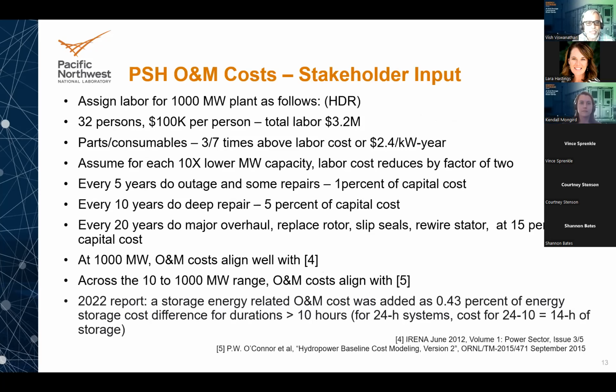For operation and maintenance cost, this is a detailed slide that we also used as a template for compressed air, so I'll go through it quickly. We assign labor for 1,000 megawatts as 32 persons at 100K per person per year, giving total labor cost. Parts and consumables are about 40% of labor cost. We assume that for each 10 times lower megawatt capacity, labor cost reduces by a factor of 2, not 10 — that's the scaling effect.